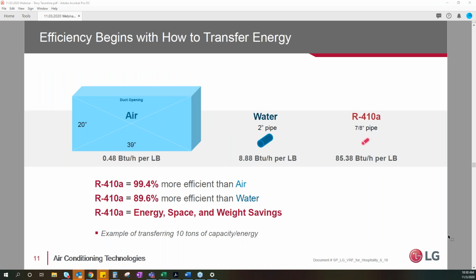And space. We talked about how small the piping was. For instance, a duct opening, again using our 10-ton example, you can see 20 by 39 versus 2-inch for water pipe and less than 1 inch for a refrigerant pipe. So again, when we're designing our building spaces, and space is money, we do have some significant advantages with water and refrigerant versus air.